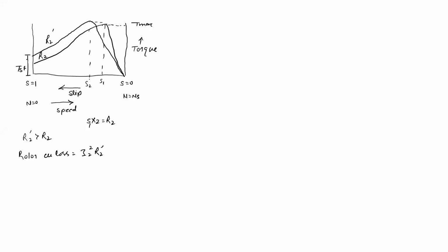Once the starting purpose is over, motor is going to work in this region. This is the region of the motor where it will work under normal working condition. So it means that the torque needed for the starting purpose is momentary. Once the purpose of starting torque is over, for example in lift, crane, and such types of loads, we do not want the high resistance to remain in the circuit as long as the motor is in running condition. So this is our objective, and this is our question: to remove that external resistance or higher resistance once the motor has started, in the normal working condition.